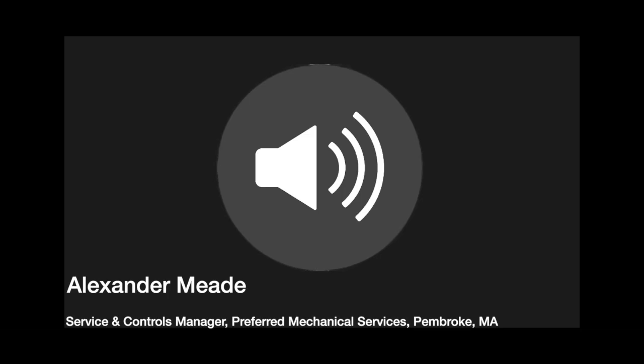So we typically would use a slab sensor, and it's kind of a misnomer because you're not going to put a temperature probe into the ice. I mean, you could, but we typically will put a slab sensor, a temperature sensor, on the bottom of a metallic cover in the ice slab itself. So that way, the sensor is essentially reading the bottom of the thickness of the ice. We find that if you use that to control what you want the slab temperature to be, then the chiller plant will maintain a glycol temperature a few degrees below that. That usually seems to be the most efficient way to do it.